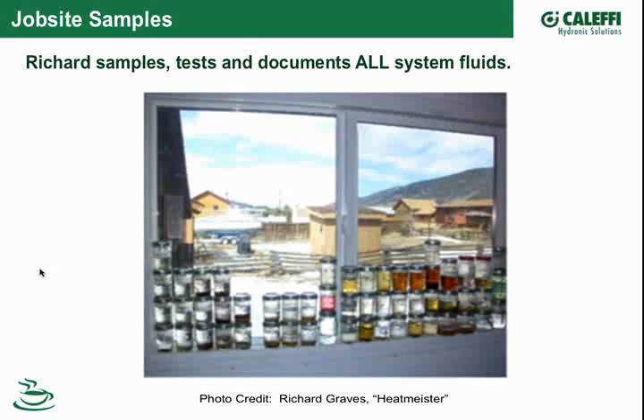This I thought is interesting, that on the job he goes on, he takes a sample of the fluid and then takes it back to the shop, and you can test it there for different things. You can see on the right there, those are all different fluids he's taken out of systems up in Colorado, and you can see the condition of the fluid. Some of them look brand new, like the one in the upper left, good and bright and clear, or colorful like it went in. Some of them are getting darker, some have sludge in the bottom, and some obviously didn't have any protection, just clear water in them.